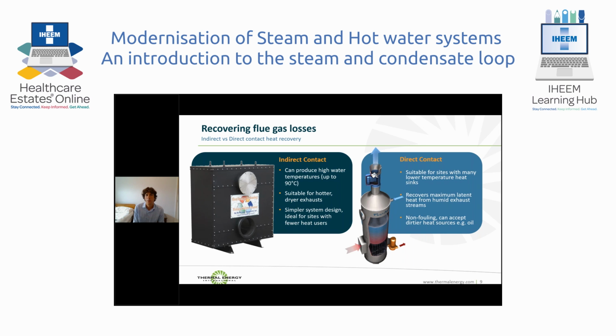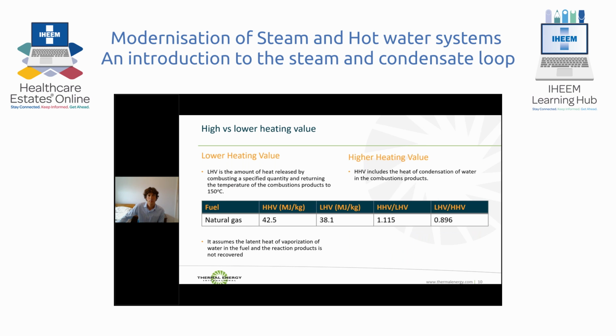Direct contact systems come into their own where we have lower temperature heat sinks available, as we do in the hospital environment. They can recover the maximum amount of latent heat from a humid exhaust stream. They're also not susceptible to fouling if you have dirtier sources. I'll talk today a lot about condensing heat recovery.